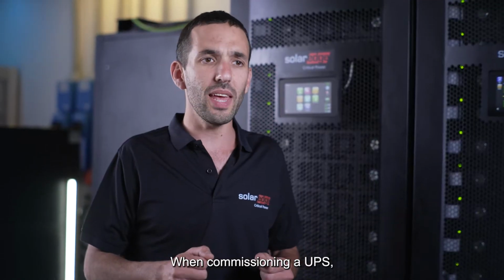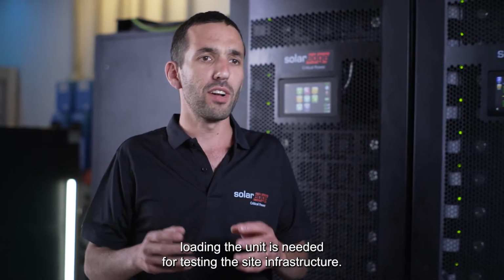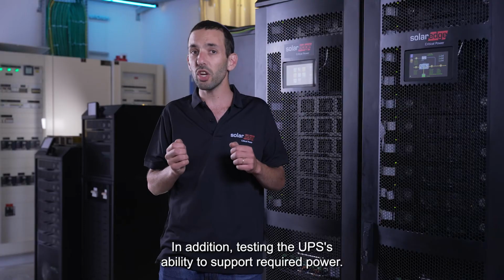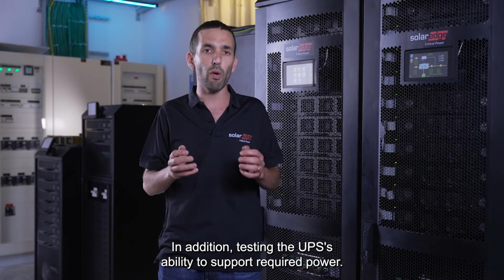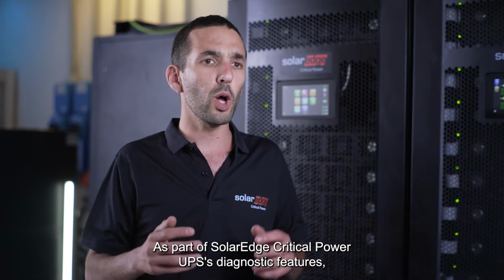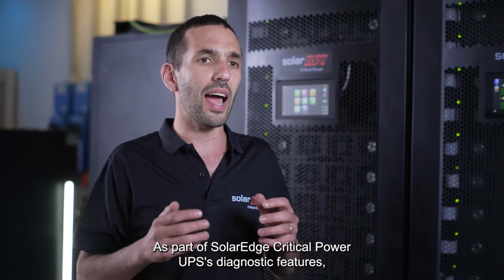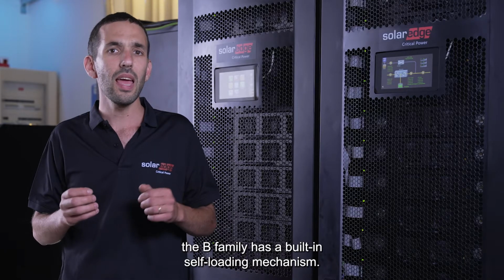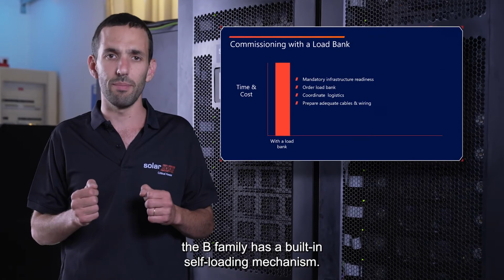When commissioning a UPS, loading the unit is needed for testing the site infrastructure. In addition, testing the UPS ability to support required power. As part of SolarEdge Critical Power UPS's diagnostic features, the B family has a built-in self-loading mechanism.